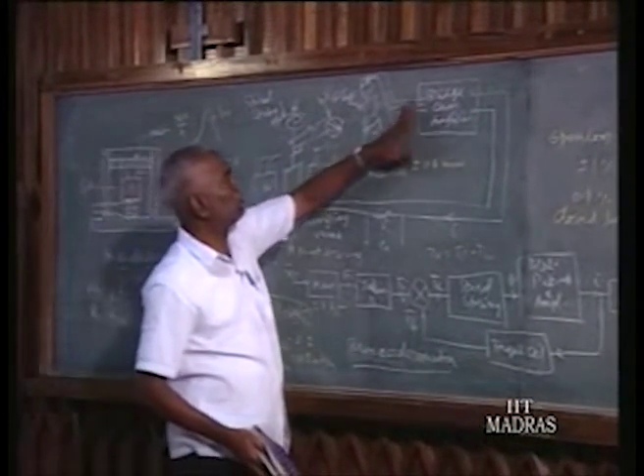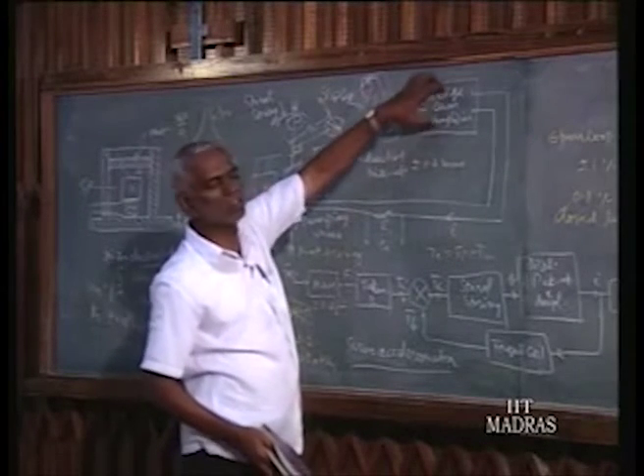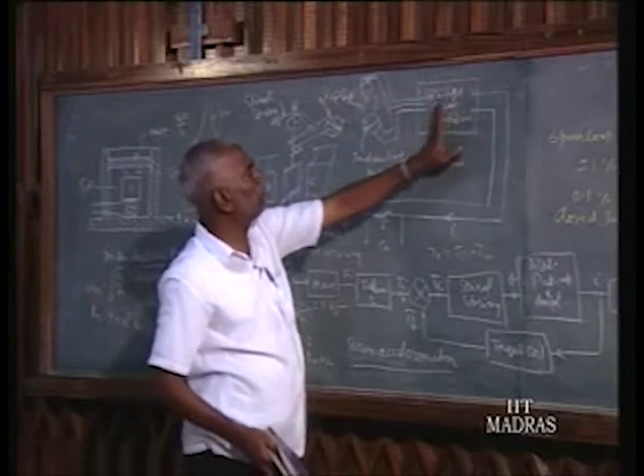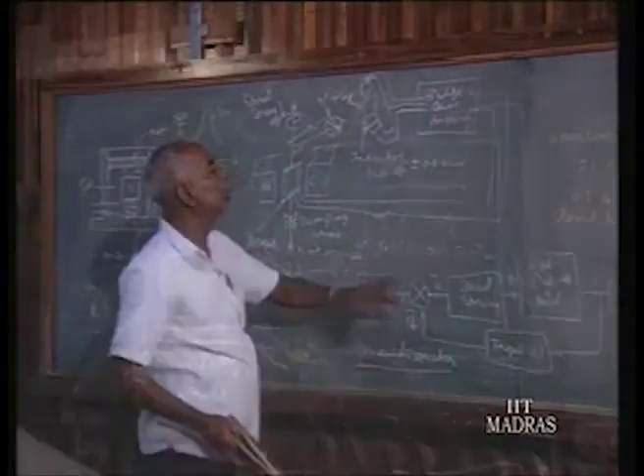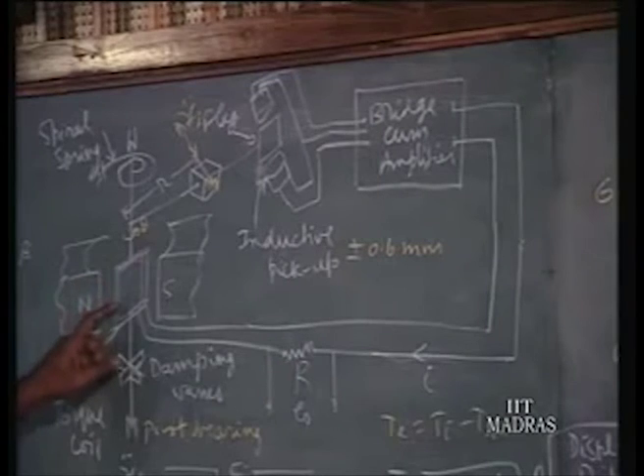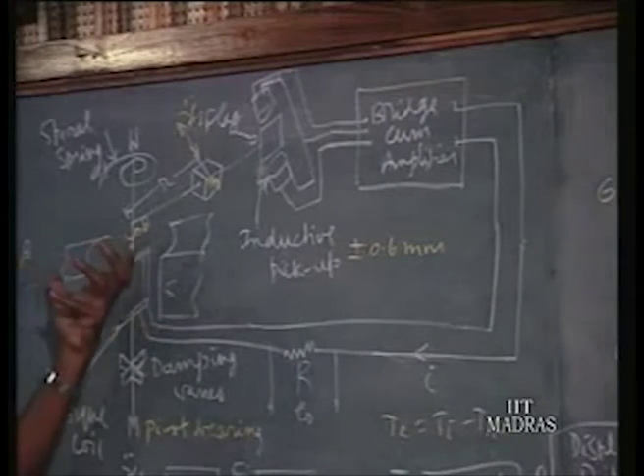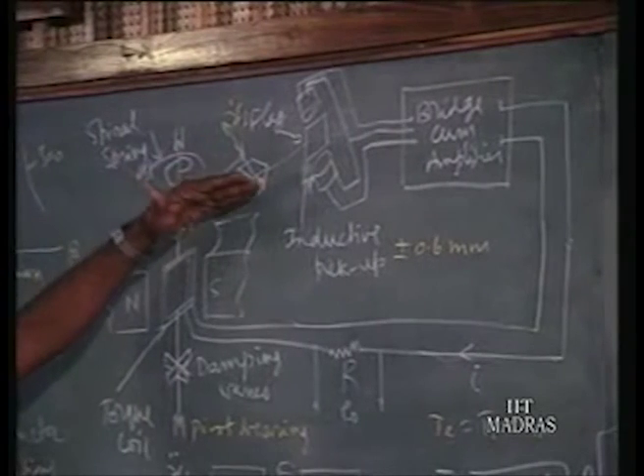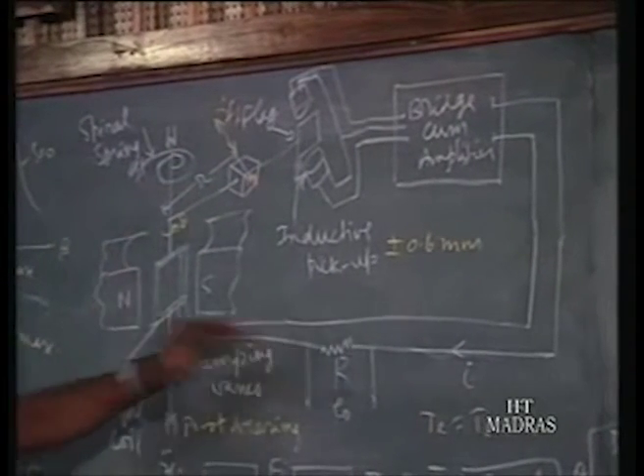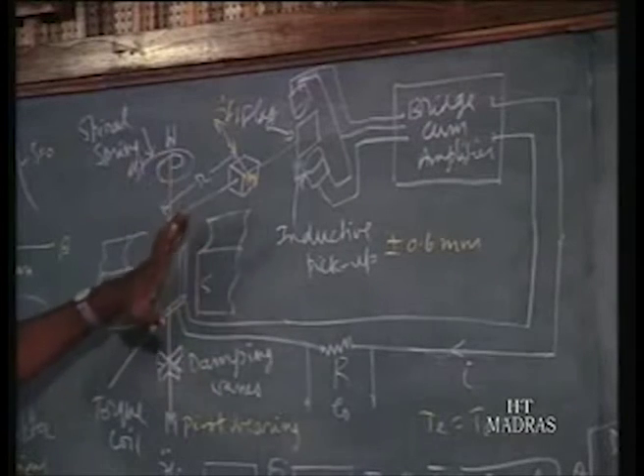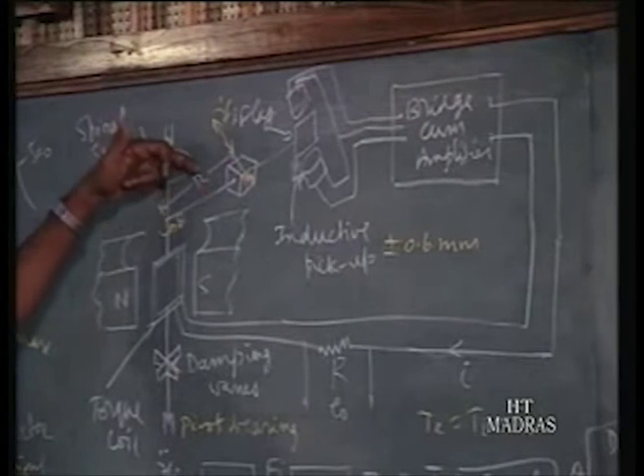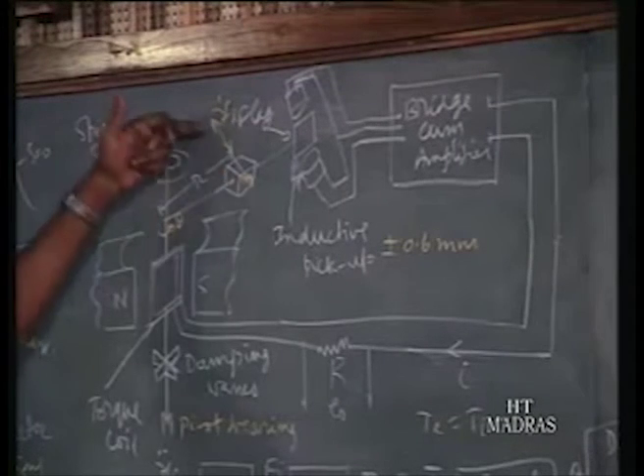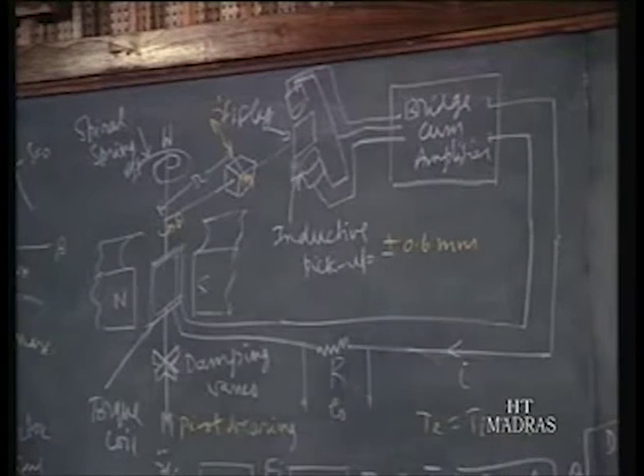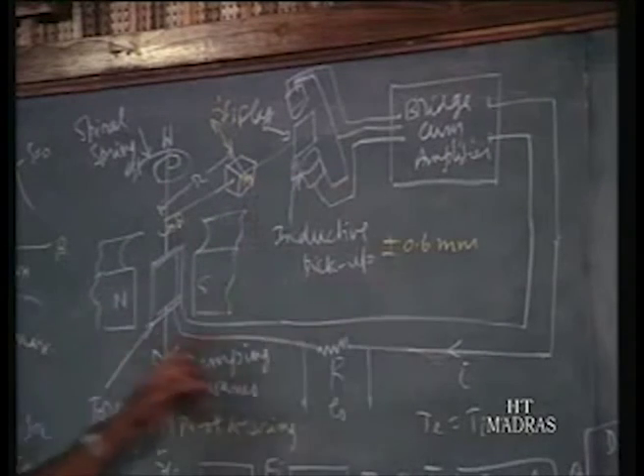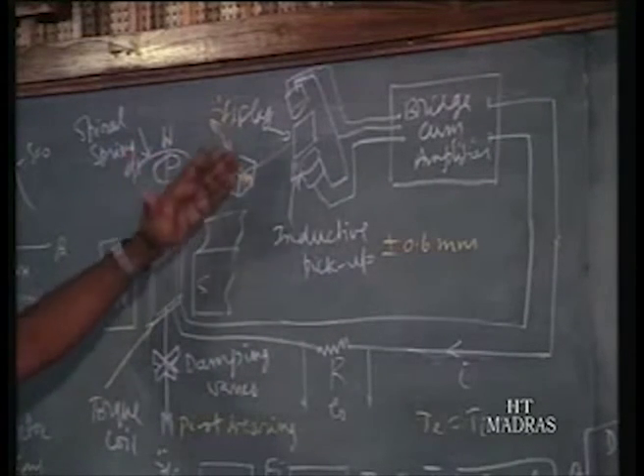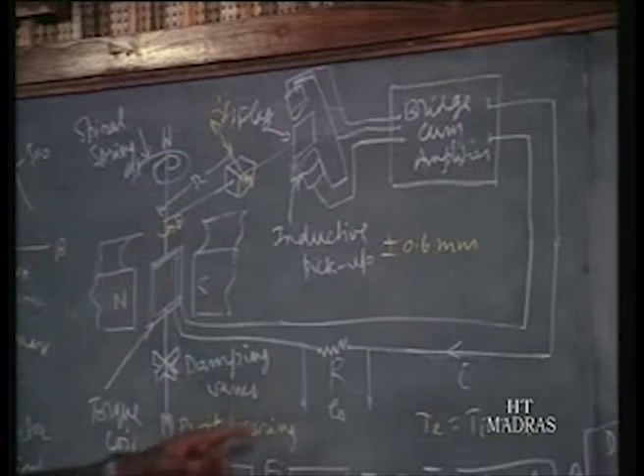The signal is amplified, it is a carrier frequency amplifier again. So from the bridge output, the amplifier gives a current output of I. This I goes through the coil, then a torque is produced in the opposite direction, trying to bring the mass back to its original position. So how much current is required to bring it back? It is a measure of the torque due to the inertia force, which again is in terms of the acceleration. So the current is maintained proportional to acceleration, so that the mass is always brought back to or near about the original position. The required current is the signal.